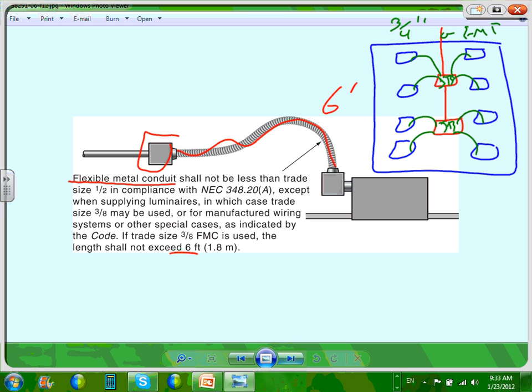So you fixture with these fixtures like this. You bring a fixture whip. They call it fixture whip. What's a fixture whip? 99% of fixture whips are going to be flexible metallic conduit. You put your conductor inside it, up to 6 feet. Here's the advantage: up to 6 feet, guys, no support, and you don't need an equipment ground conductor. So you just put 2 wires inside that baby, and you fixture whip it.